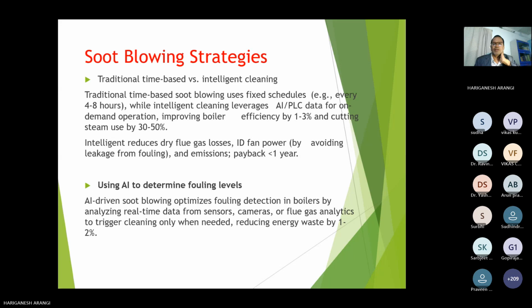Using AI to determine fouling levels, AI-driven soot blowing optimizes the fouling detection in a boiler by analyzing real-time data from sensors, cameras, or flue gas analytics to trigger cleaning only when needed, reducing the energy waste by 1 to 2%. Normally, in industry practice, soot blowing is operated every 4 hours, 8 hours. If it is AI driven, there will be cameras monitoring how much ash is accumulated. If no ash is accumulated, there is no need to do the soot blowing.